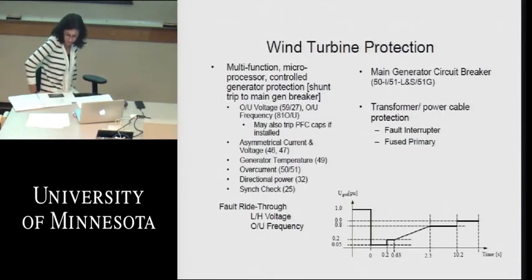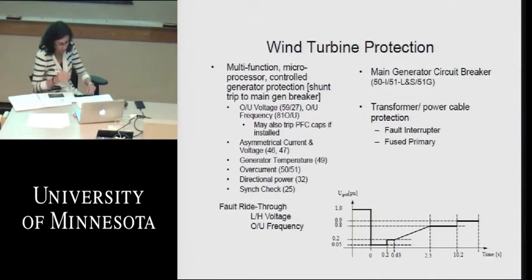Just quickly, this shows the type of protections we put into the wind turbine itself. Again, with that top controller, that multifunction microprocessor, it has all the protection capabilities, all the protection relay capabilities already built into the wind turbine. So you've got over and under voltage and frequency protection, asymmetrical current, meaning the three phases aren't balanced properly. The temperature on the transformers and the generator needs to be monitored.